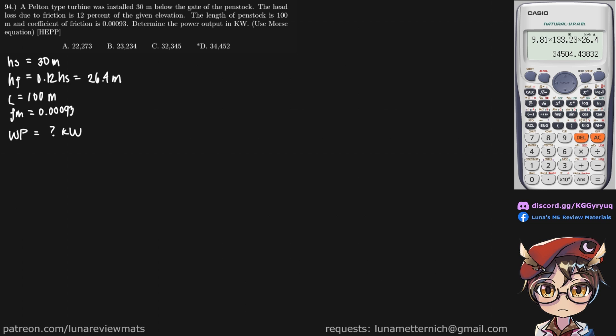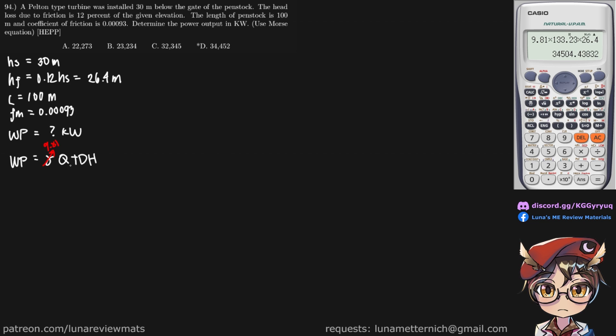To find our power output, we know that WP is equal to gamma times the volumetric flow rate Q times the total dynamic head. And this is simply 9.81. So we need to find our Q and our TDH.